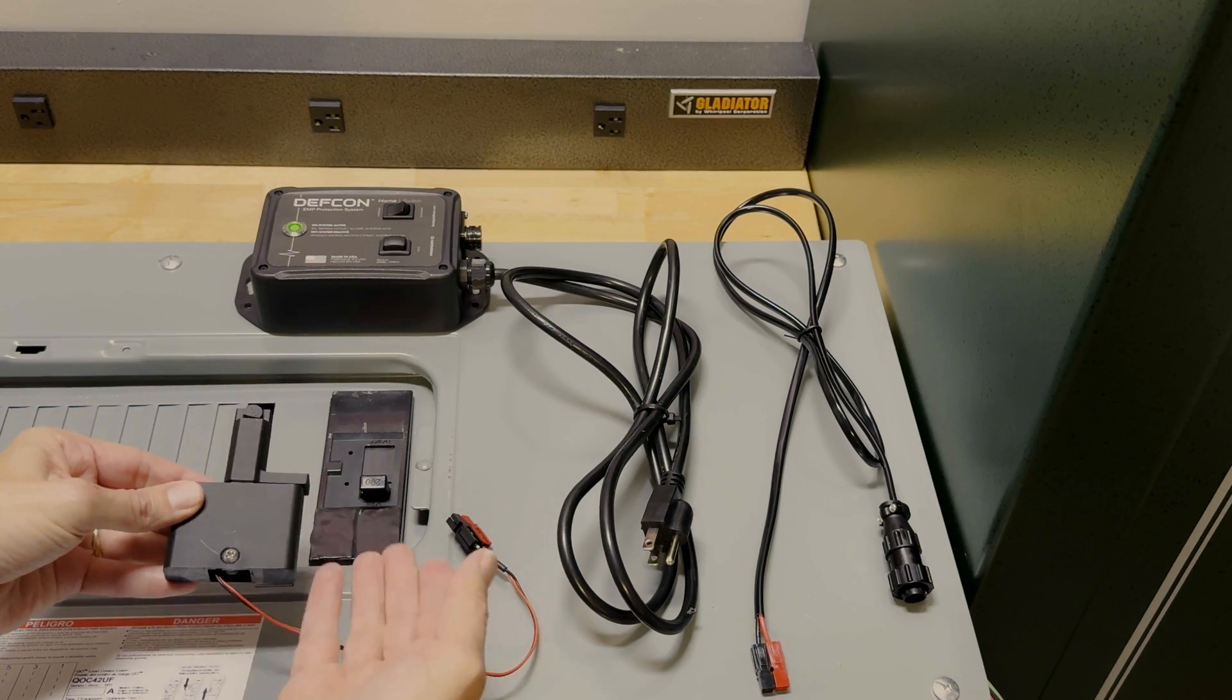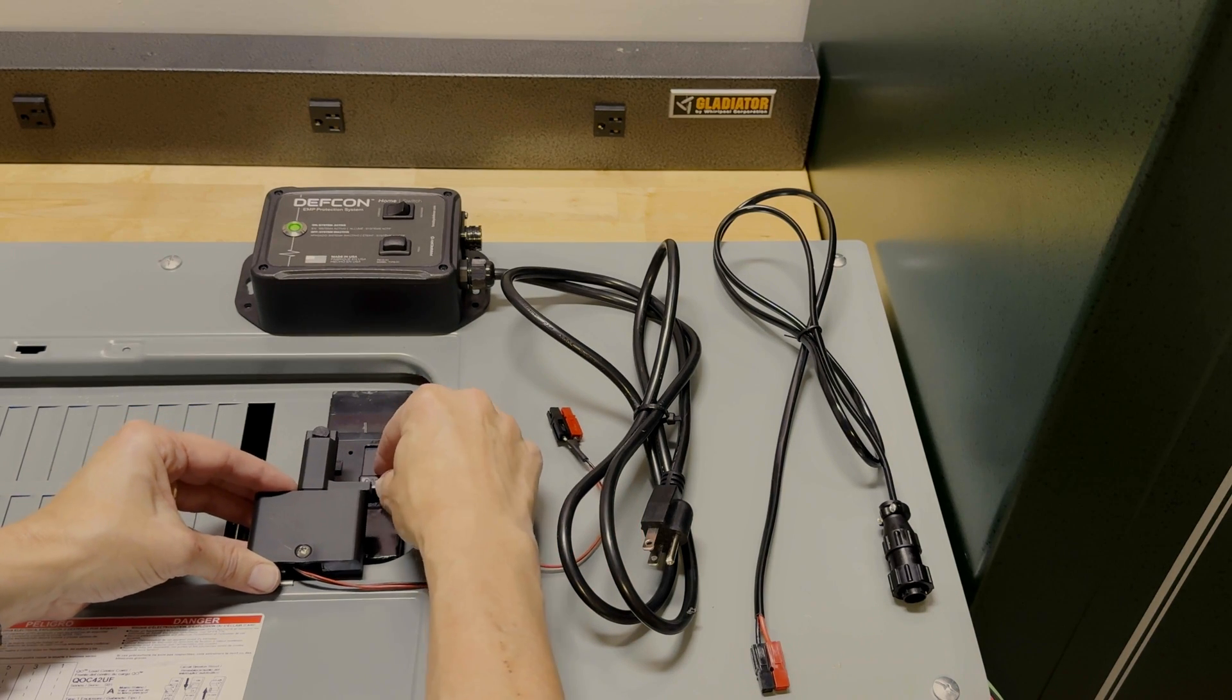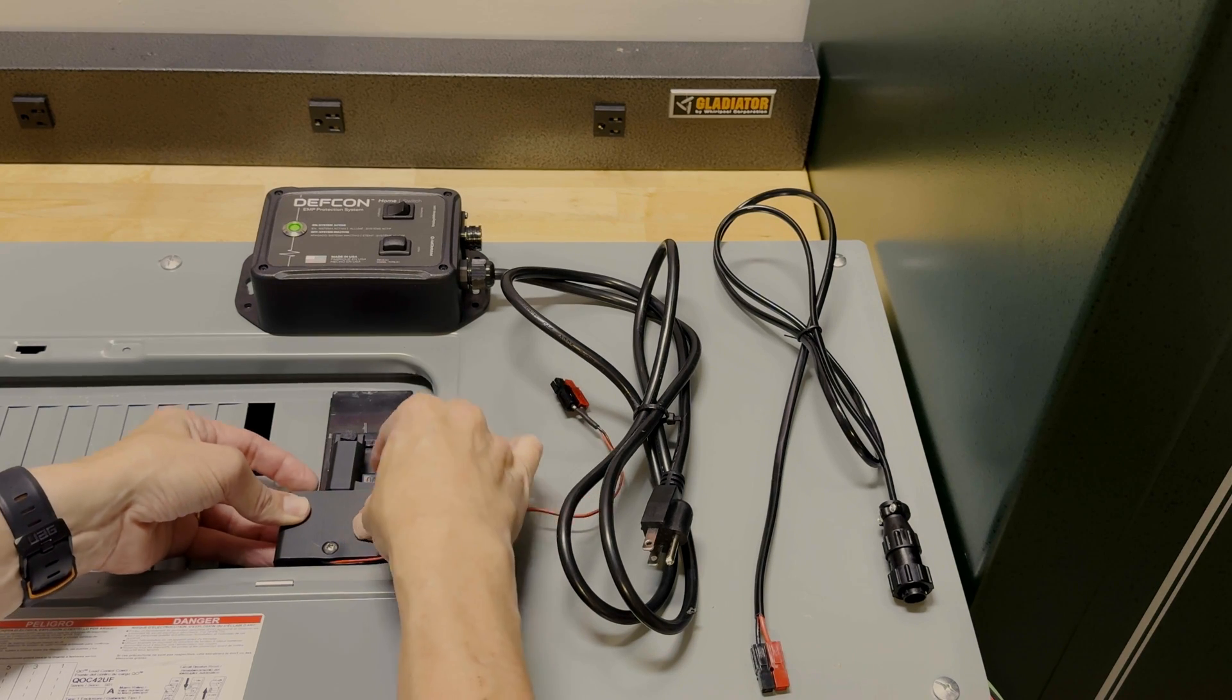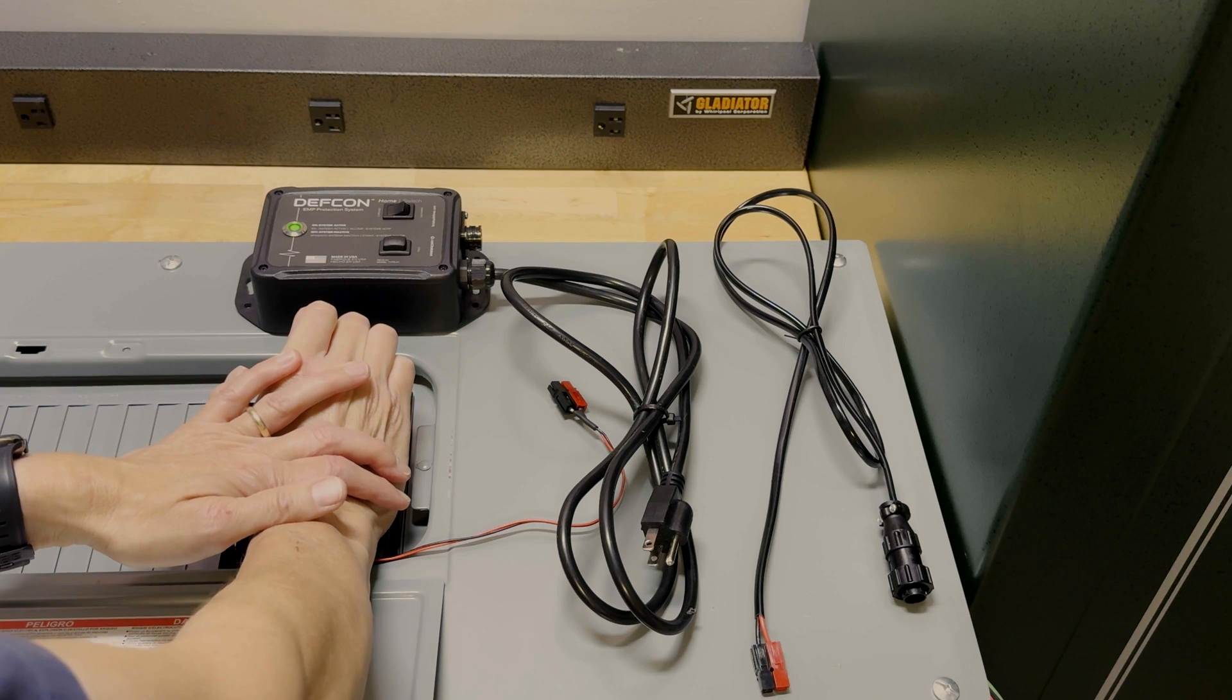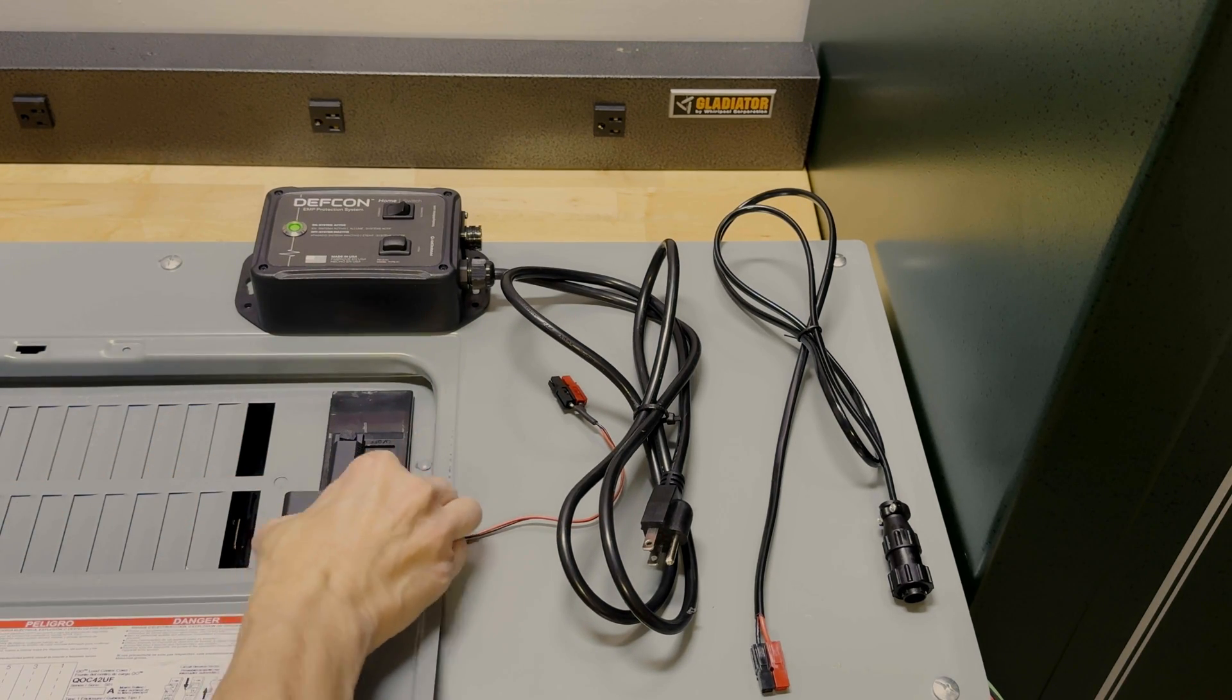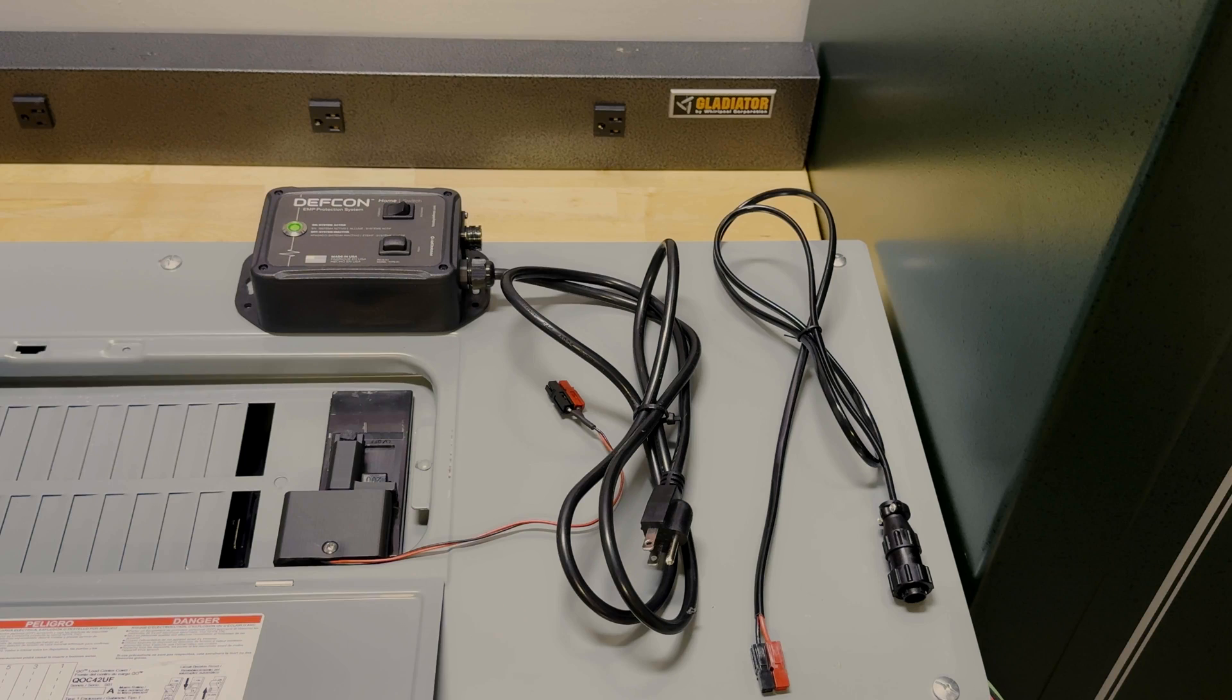The screw goes face up when you're attaching it, so don't turn it upside down like that. So face up and what you're going to do is you're going to try and align it as straight as you can but not interfering with the breaker. You don't want to push the breaker part of the way already with the actuator stowed. So I'm going to line it up here as straight as I can and then you're going to push it and hold it in place for about 30 seconds or so and just kind of put some pressure on it. Once this tape sets up, it's very difficult to pull it off, so we just want to make sure it's nice and well attached here. So once it's attached, you'll notice it doesn't move at all. The idea again is this actuator assembly will drive the breaker and trip the breaker under certain conditions. So that's the first step, to get that actuator assembly attached.